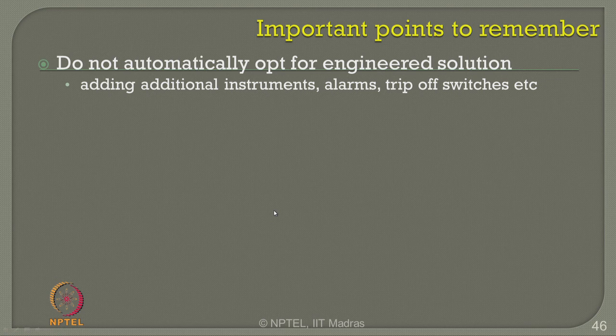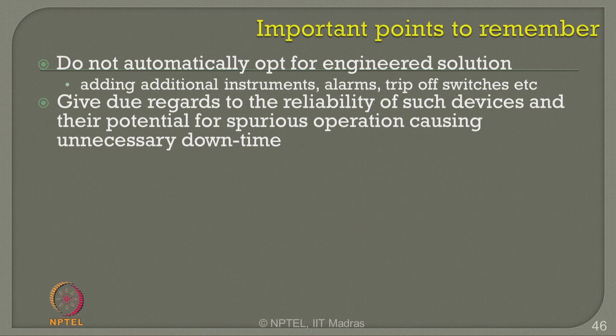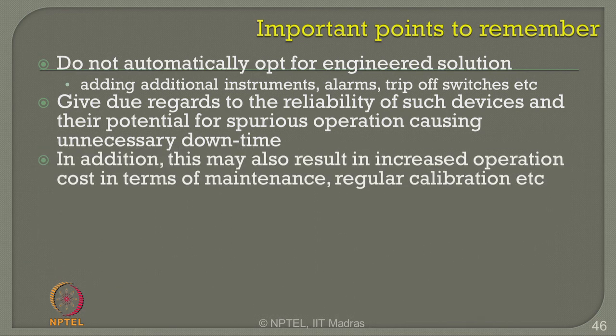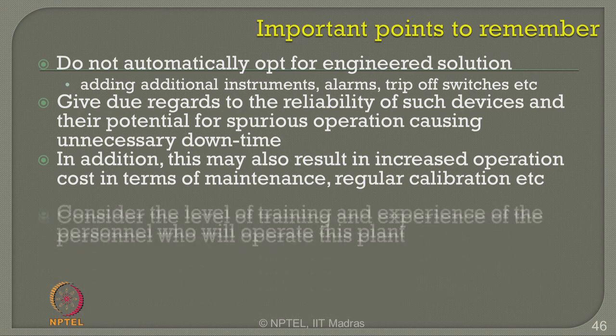Now, let us discuss a few important points to be remembered while writing a HAZOP report. Do not automatically opt for engineered solutions. Adding additional instruments, alarms, trip switches, etc. is not a good recommendation for a HAZOP report. Give due regard to the reliability of such devices and their potential for spurious operation. In addition, this may also result in increased operation cost because the maintenance schedule and regular calibration will all be affected if you recommend additional instruments in a given P&ID.